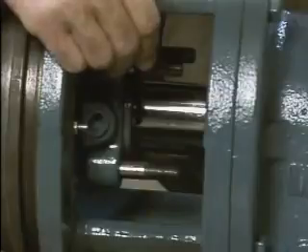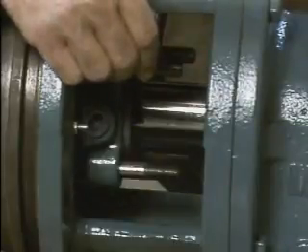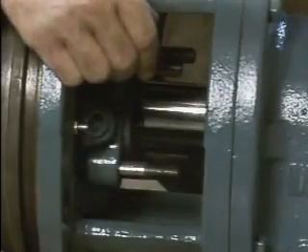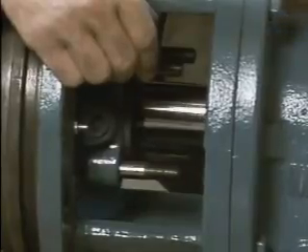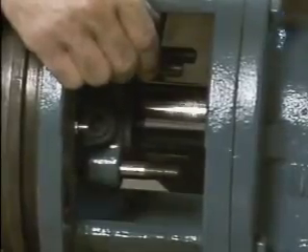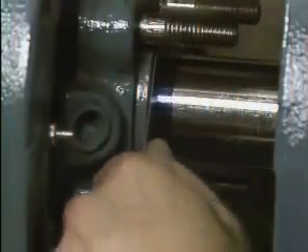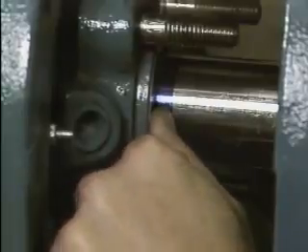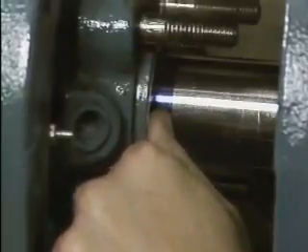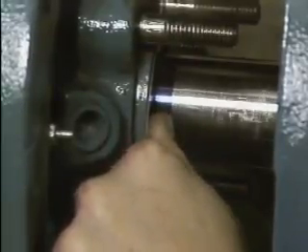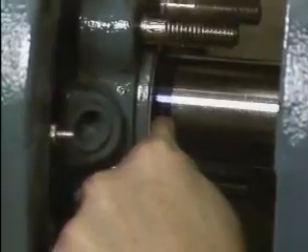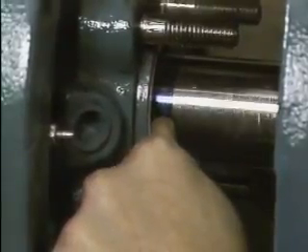After the impeller clearance has been measured, the shaft sleeve is marked so that the rotating element can be positioned properly later. This is done by first applying bluing to the shaft sleeve along the edge of the stuffing box. Then a line is scribed in the bluing to mark the edge of the stuffing box. This line is a reference line for positioning the seal's rotating element. Once the line is marked, the pump components are disassembled again.